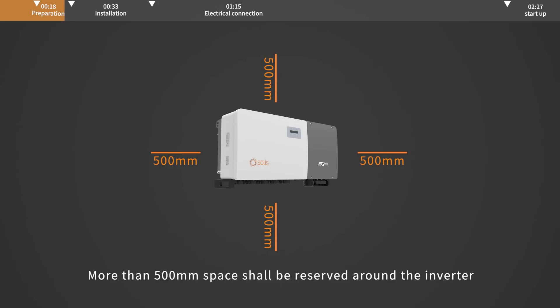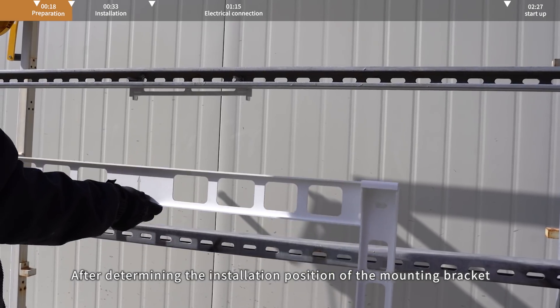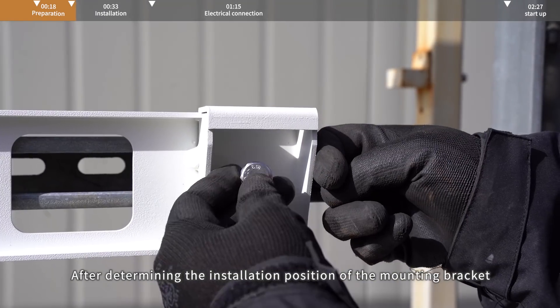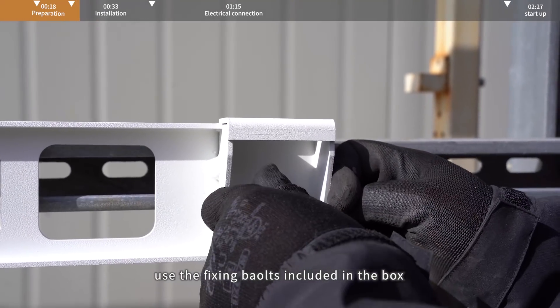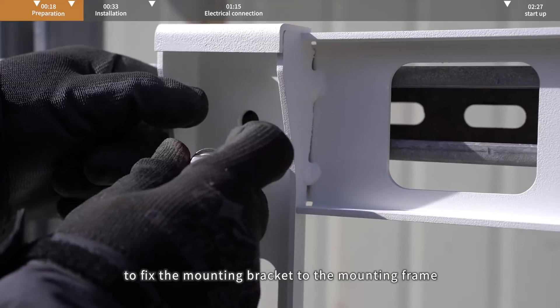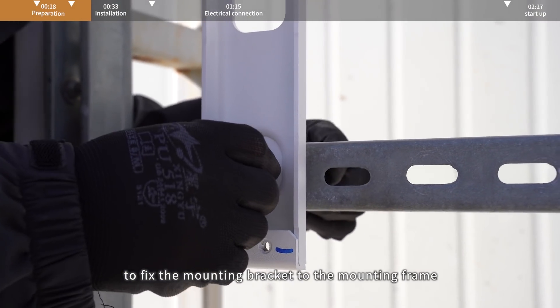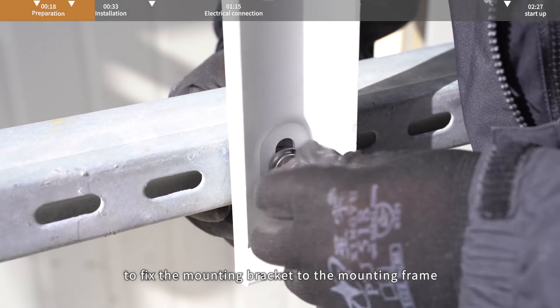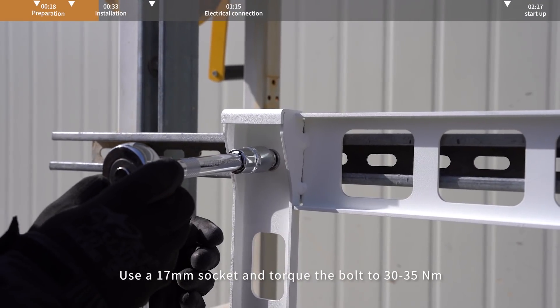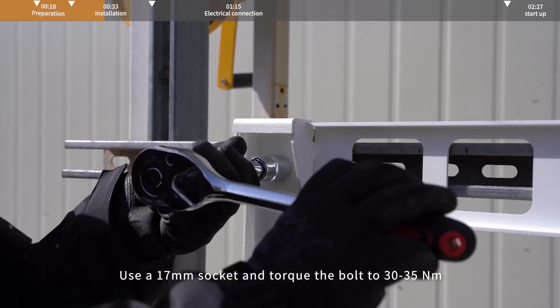More than 500 mm space shall be reserved around the inverter after determining the installation position of the mounting bracket. Use the fixing bolts included in the box to fix the mounting bracket to the mounting frame. Use a 17 mm socket and torque the bolt to 30-35 Nm.